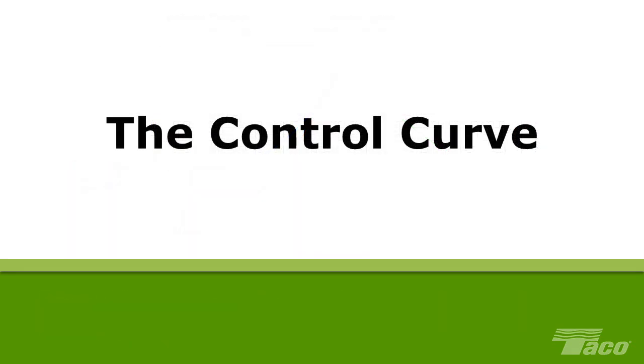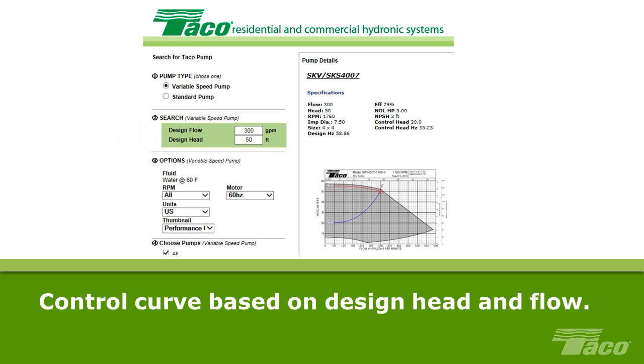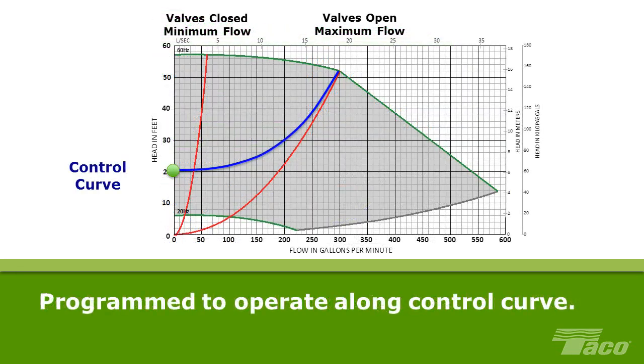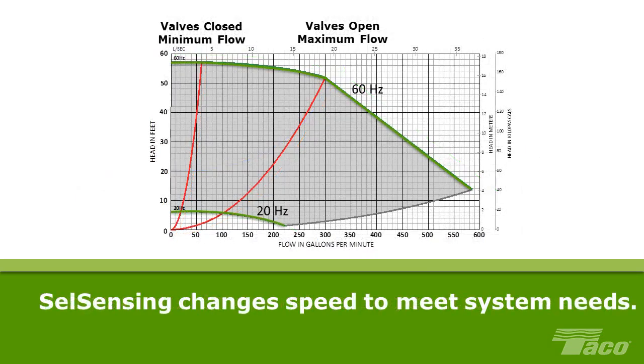The control curve. The control curve is based on the design head and design flow provided by the purchaser when the pump is ordered. The pump is programmed to operate along this control curve to provide the greatest energy efficiency in a particular application. If the pump operates along a curve of any other shape, it will be less energy efficient. As we said earlier, a self-sensing pump changes its speed to accommodate the needs of the system at any given time. Let's see how that works.